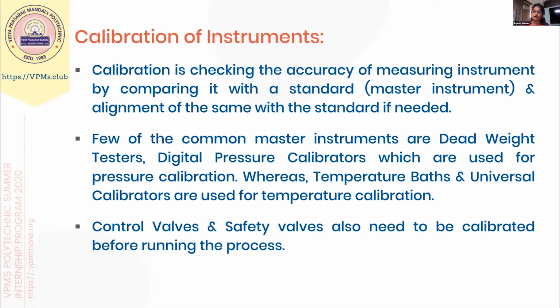Then the main activity is calibration of instruments. What is calibration? You must have studied. It's checking the accuracy of a measuring instrument by comparing it with a standard instrument. We call it a master instrument. Many times, if the output is not proper or it is not working properly, alignment is done in comparison with the standard. A few of the master instruments usually used in industry are the deadweight tester and digital pressure calibrators, which are used for pressure calibration. Then temperature baths and universal calibrators are used for temperature calibration. Control valves and safety valves, as I showed you in an earlier slide, also need to be calibrated before coming into the process line.